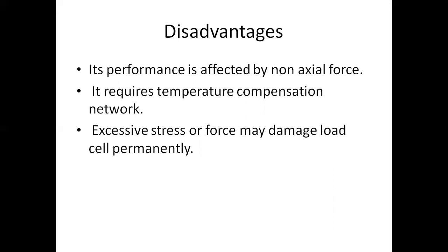When we talk about the disadvantages, it requires continuous electrical energy for the production and display of signals. It cannot be used for pressure measurement of highly reactive or corrosive materials because they can damage the gauge. It also requires an amplification circuit for the output display because the signals produced by the gauge itself are very low voltage, almost in millivolts, and it requires temperature compensation networks. Its performance is affected by non-axial force. Excessive stress or force may damage the load cell permanently.